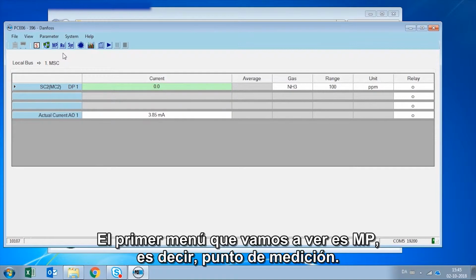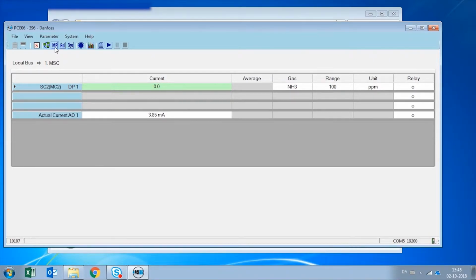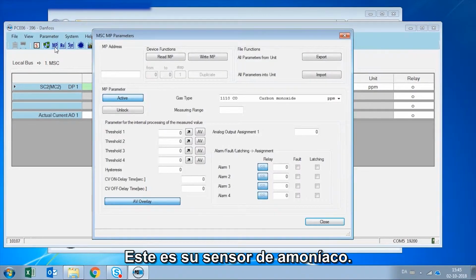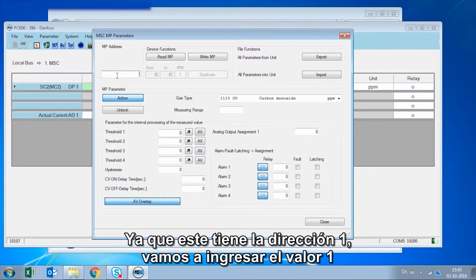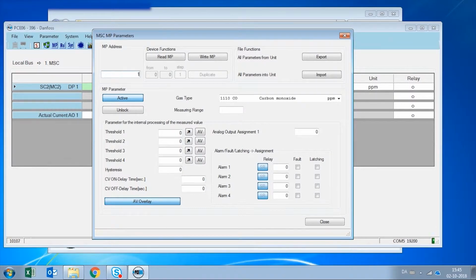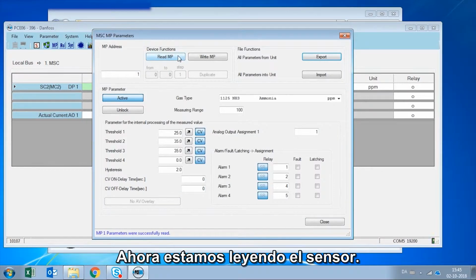The first menu we are going to take a look at is the one called MP, which is measuring point. This is your ammonia sensor, and since this one has the address 1, we are going to enter the value 1 and click read measuring point. Now we are reading the sensor.